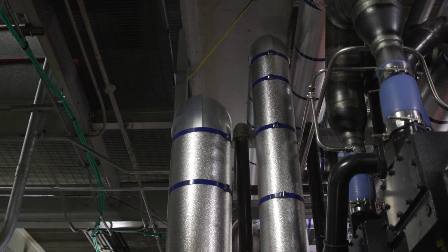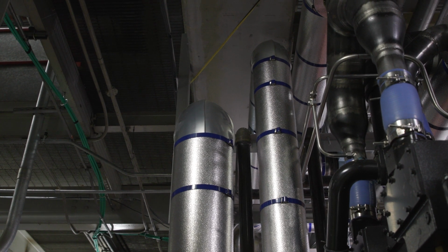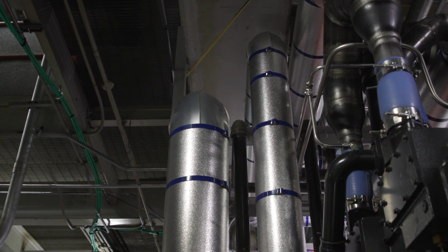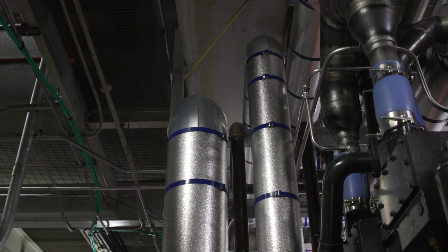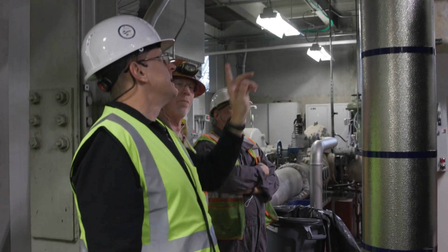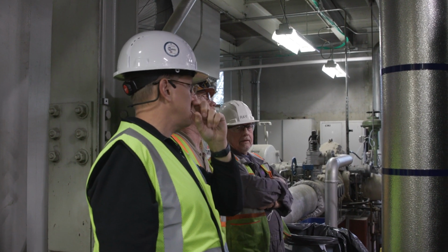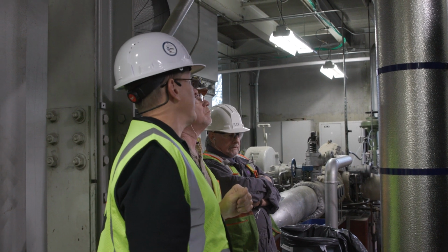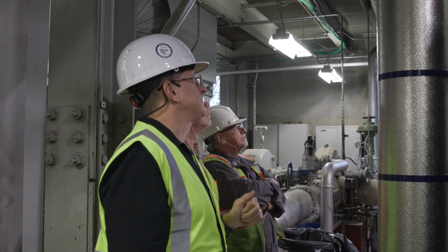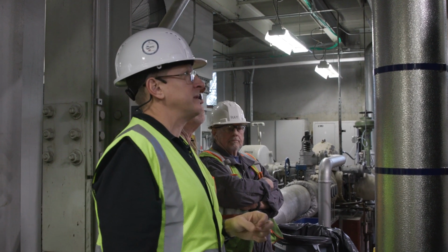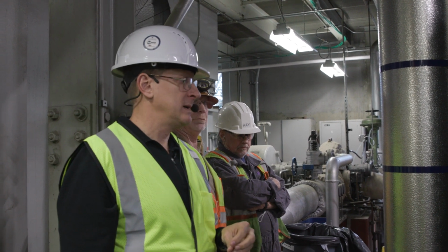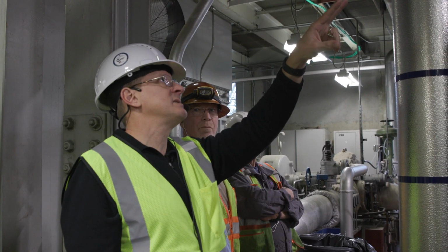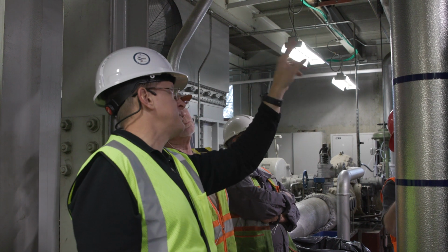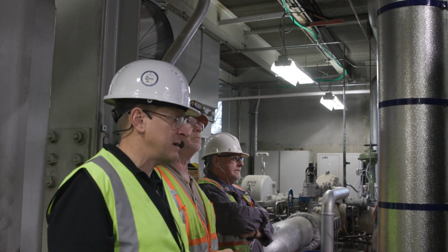I don't think we'll take a trip to see the radiator, but on your own time you can go take a look at it. It's a standard, typical radiator. Notice all the isolation valves that obviously have to be open unless you're doing some kind of service to the cooling circuits. You've also got some vent line connections from the engine that go up to the airspace of the expansion tank of the radiator.